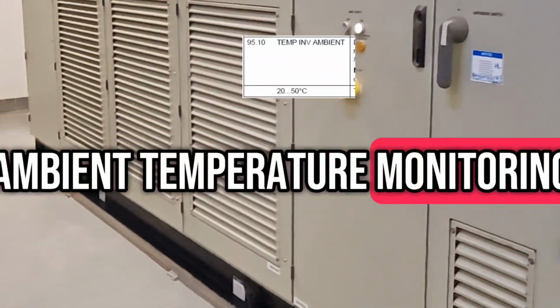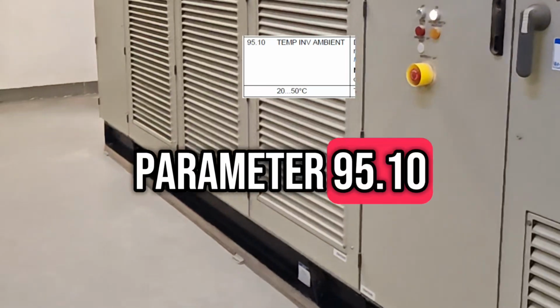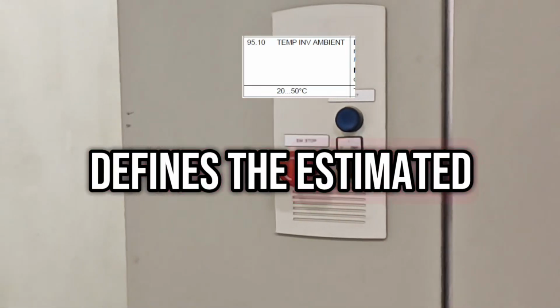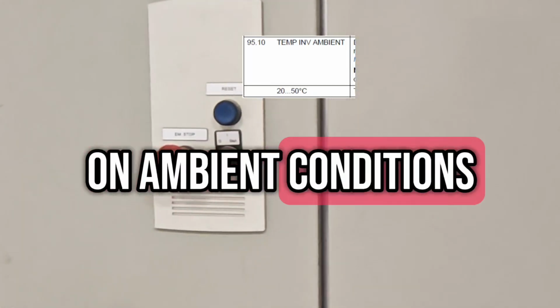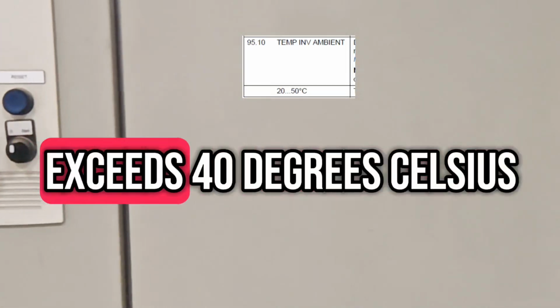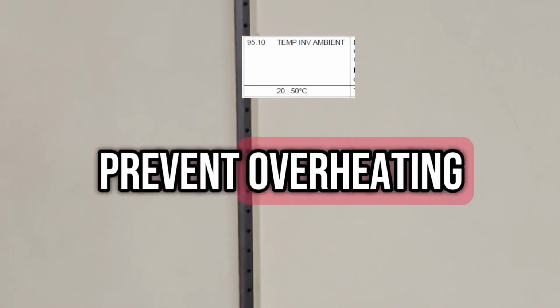Ambient temperature monitoring. Parameter 95.10 defines the estimated IGBT temperature based on ambient conditions. If the environment exceeds 40 degrees Celsius, adjust this setting accordingly to prevent overheating.